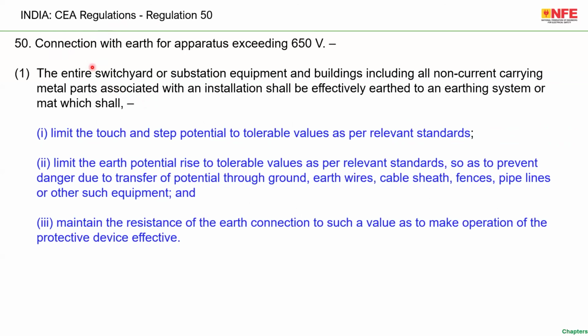Regulation 50, sub-regulation 1 and sub-regulation 1.1 limit the touch and step potential to tolerable values as per the relevant standard. So the first requirement is touch and step voltages must be lesser than the recommendation in the standard. The reason is people or animals should not get shocked. People should not get shocked. Of course, not animals. People should not get shocked. That is the first requirement.